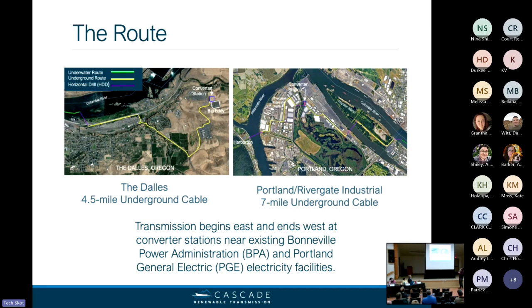At that point, we will pull conduit, HDPE conduit that's large enough to hold our cable, back into what's called a drill pit. At that point, we'll create a transition joint. That transition joint will allow us to connect the submarine style cable to the underground cable, something we've done before as well. So this is the point where we make the transition from submarine into upland cable.